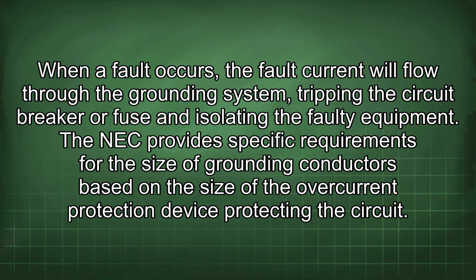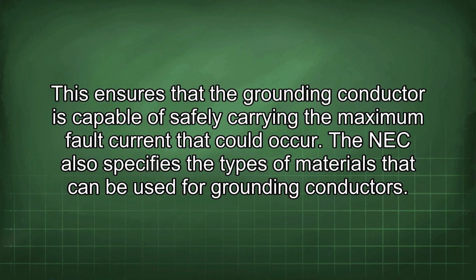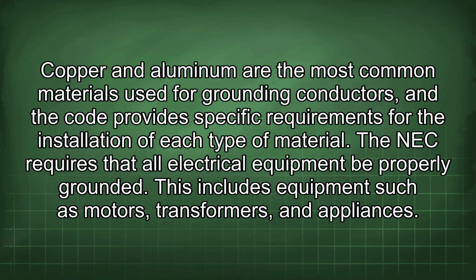isolating the faulty equipment. The NEC provides specific requirements for the size of grounding conductors based on the size of the overcurrent protection device protecting the circuit. This ensures that the grounding conductor is capable of safely carrying the maximum fault current that could occur. The NEC also specifies the types of materials that can be used for grounding conductors. Copper and aluminum are the most common materials used for grounding conductors, and the code provides specific requirements for the installation of each type of material.